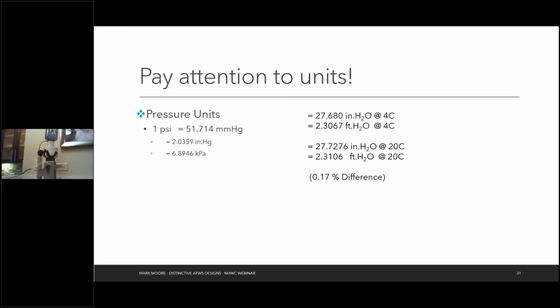And so when we're using pressure transducers to go from pressure to water depth, the temperature of the water is actually pretty important. For these PTs, pretty much anyone out there on the market is going to have a temperature compensator in there to adjust for this, because it's 0.17% different. And we're only allowed 0.1% full scale error. So that would throw us out of accuracy if we didn't account for temperature changes. Just something I wanted to put out there and something to be aware of.